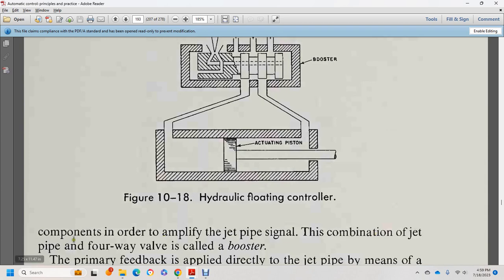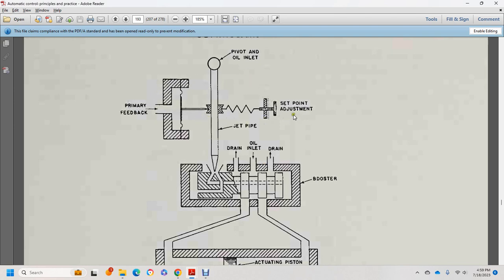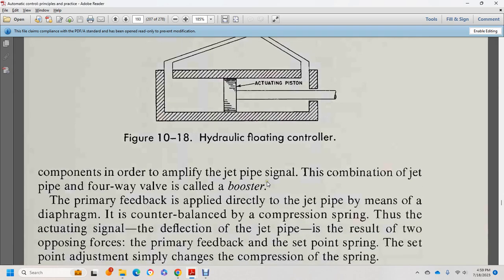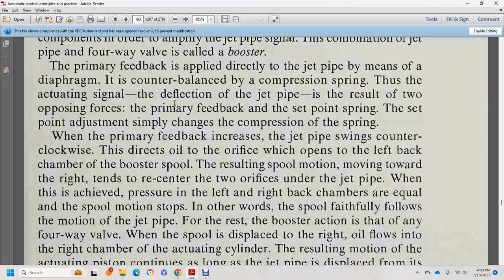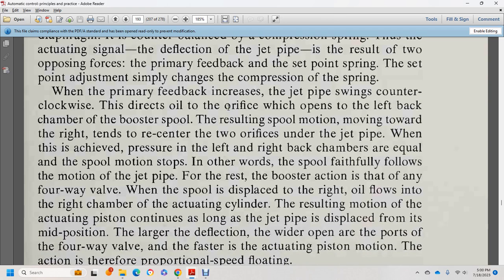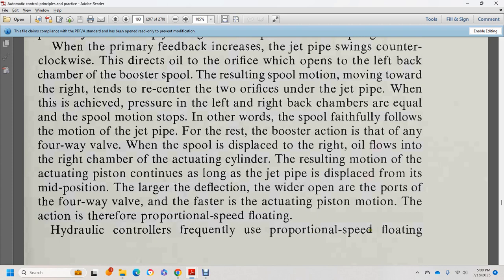The combination of the jet pipe with the four-way valve is called a booster. Components include: pivot and oil inlet, primary feedback, jet pipe, set point adjustment, drain, oil inlet, drain, and actuating piston. Primary feedback is applied directly to the jet pipe, which is counter-balanced by a compression spring. The actuating signal deflects the jet pipe. The two opposing forces — primary feedback and set point spring — determine the position. The booster spool moves, directing oil to one side of the actuating cylinder. The spool faithfully follows the motion of the jet pipe, making this a proportional speed floating hydraulic control.